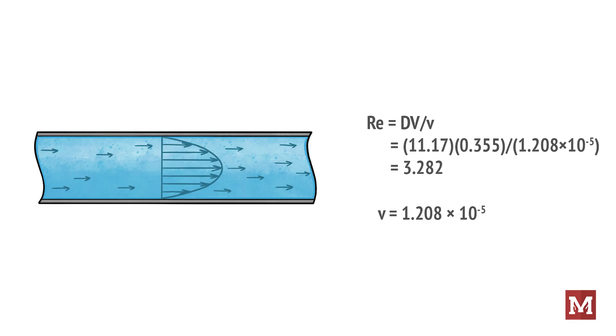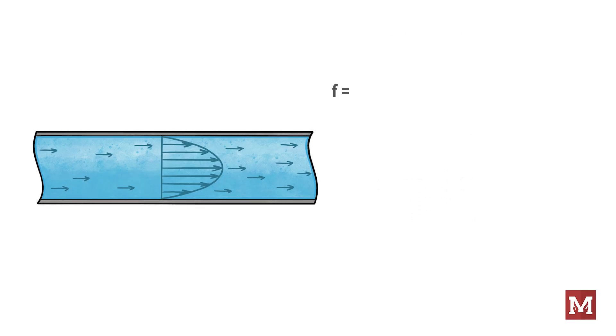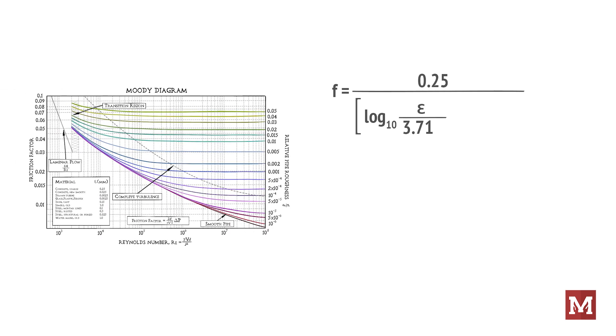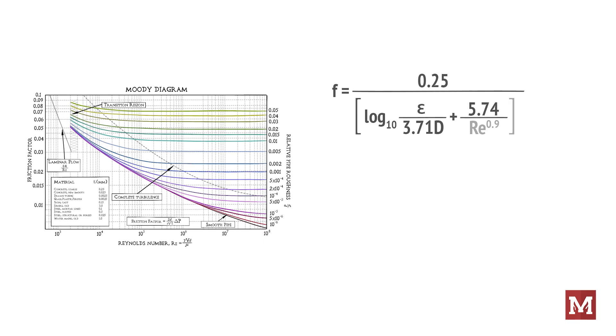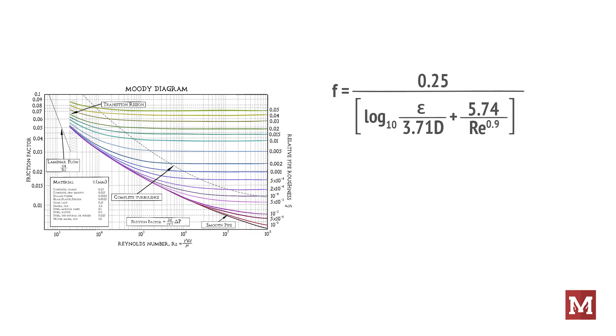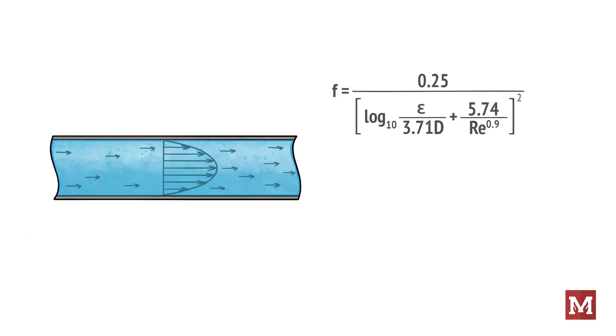If we take that information and plug it into the Jain equation we would then have calculated the friction factor for this pipe. The Jain equation is 0.25 divided by the log to the base 10 of the ratio between epsilon, the roughness, divided by 3.7 times the inner diameter of the pipe plus 5.74 divided by the Reynolds number raised to the 0.9th power. All of that is squared. So a bit of an equation, but the result from that helps us define what's typically going on here.